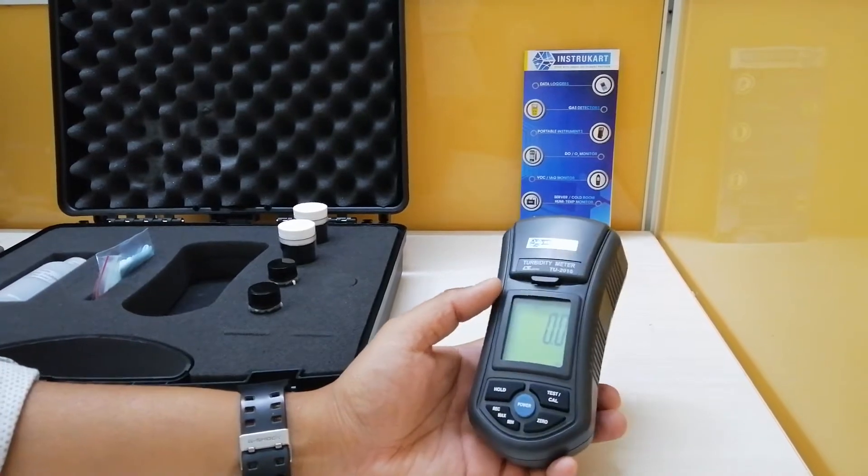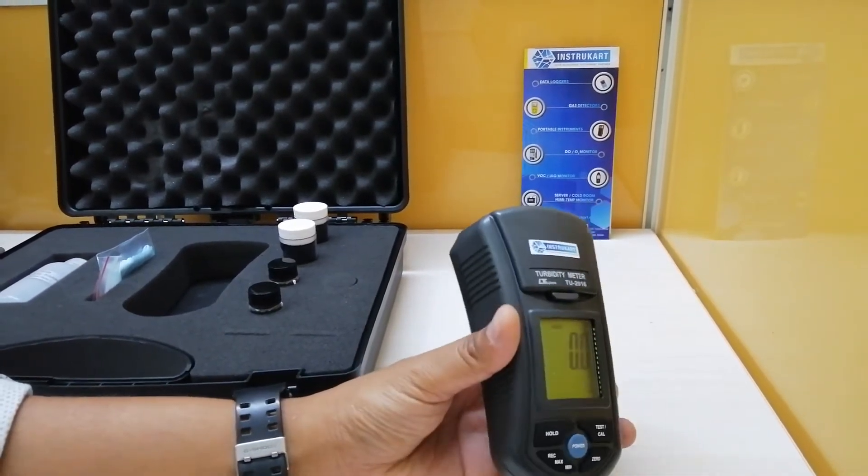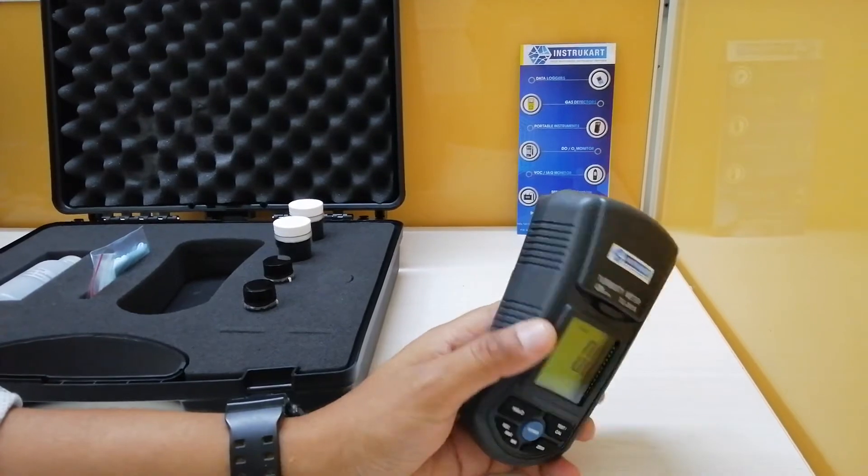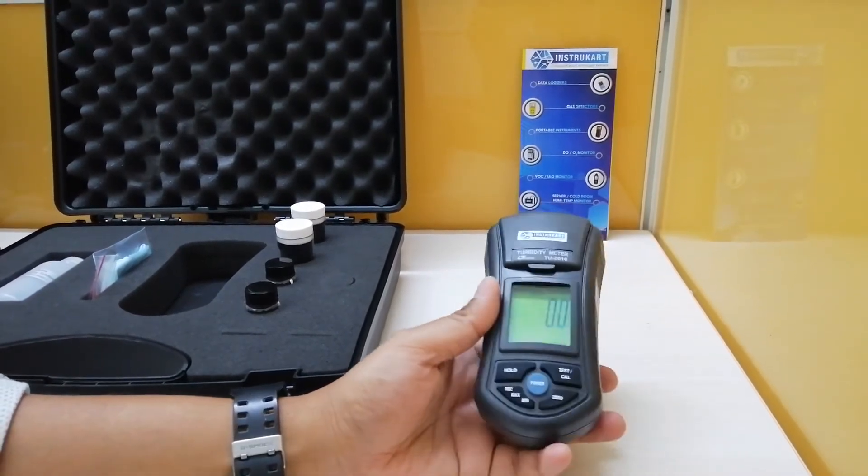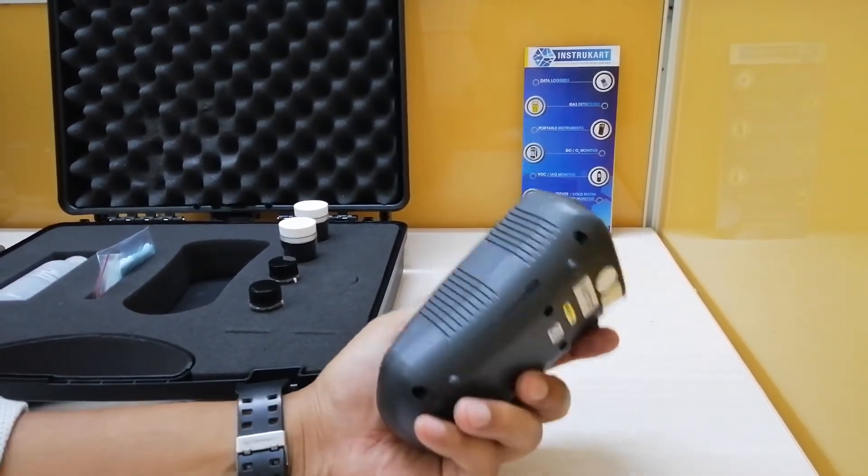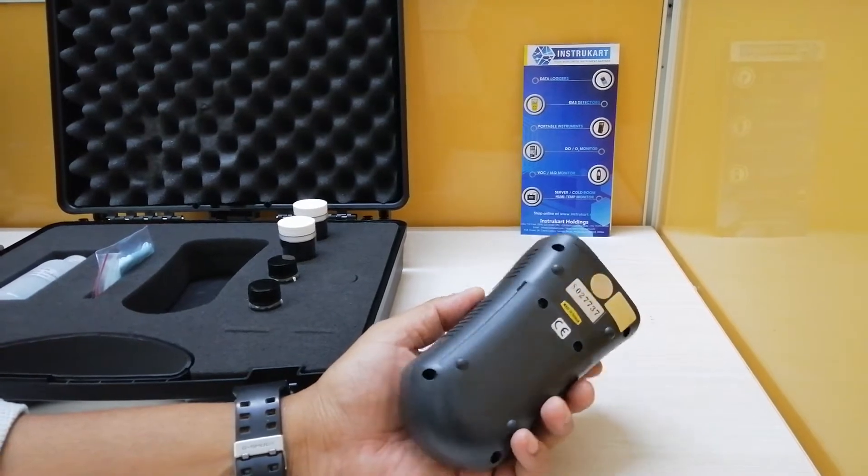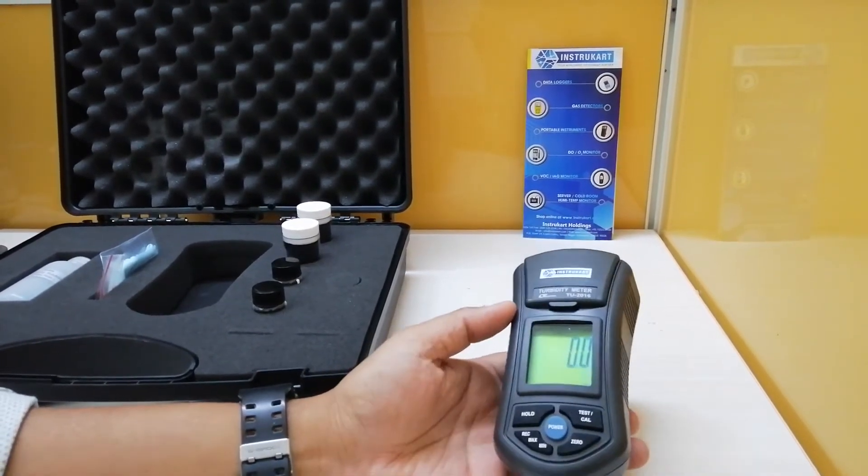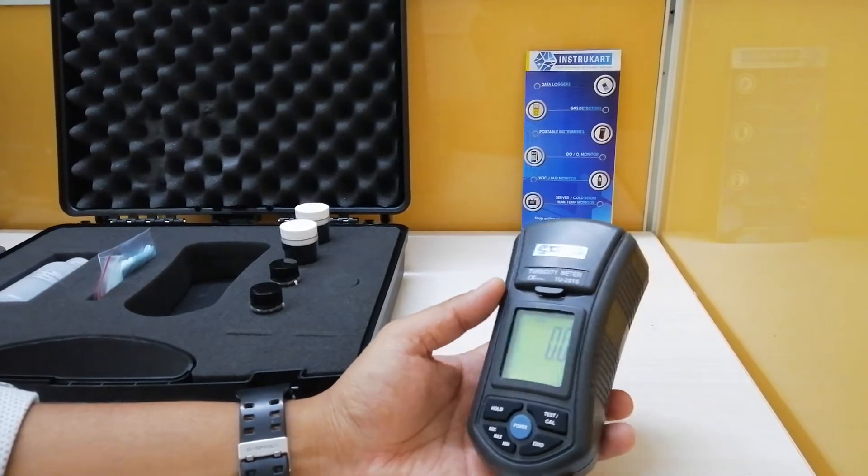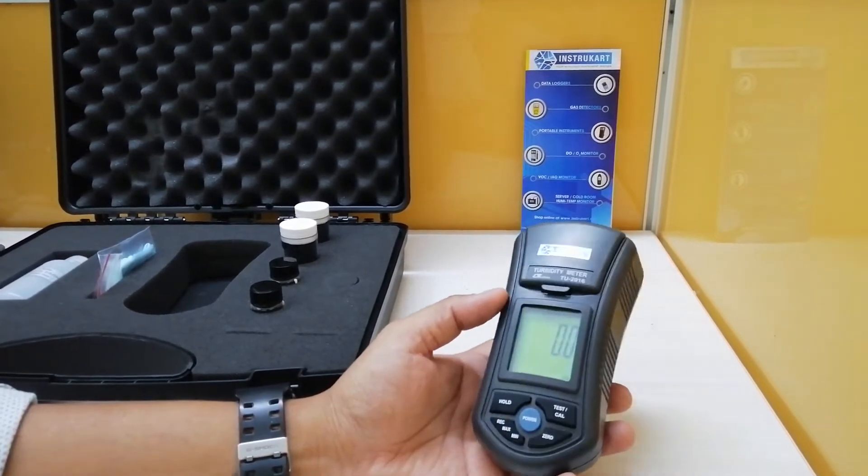The light source is an LED at 850 nanometers, and the detector is a photodiode. It meets the standard ISO 7027 for the testing procedure, and the response time for this meter is less than 10 seconds.